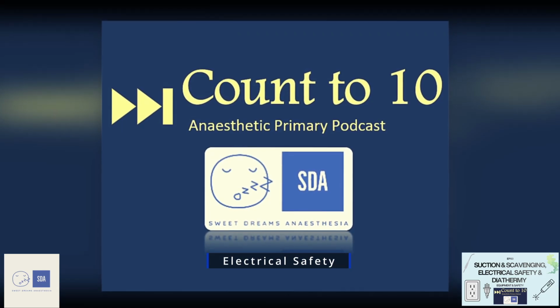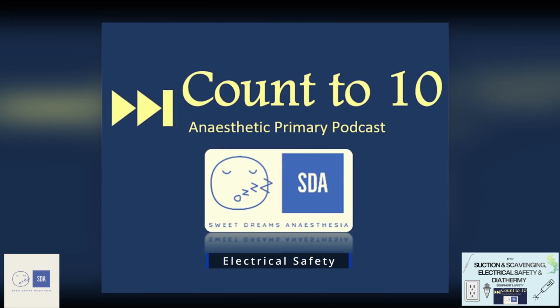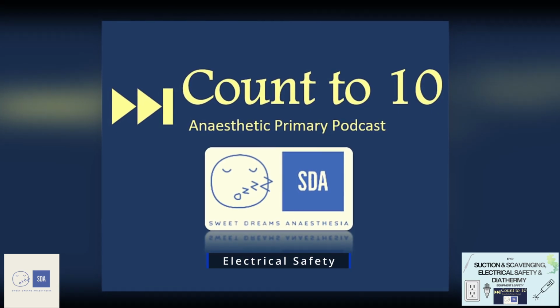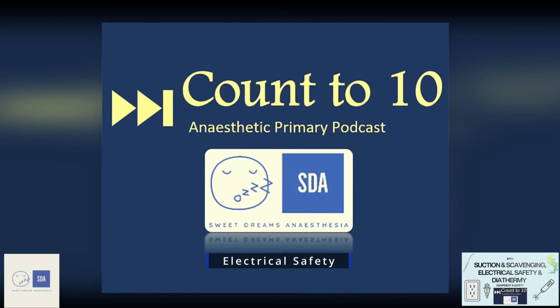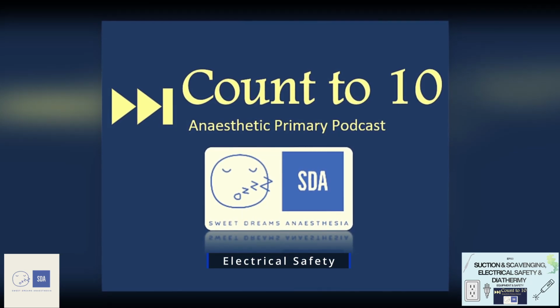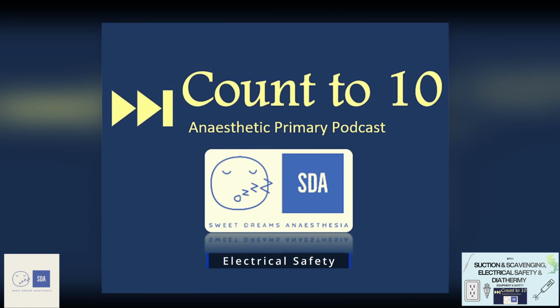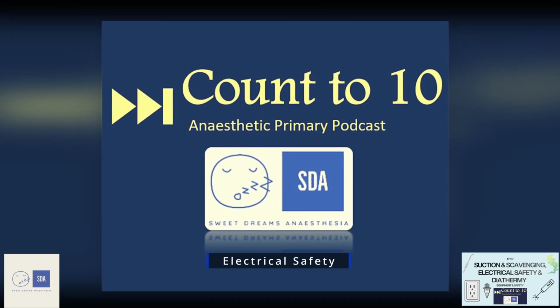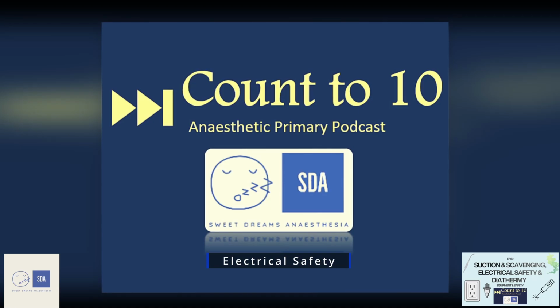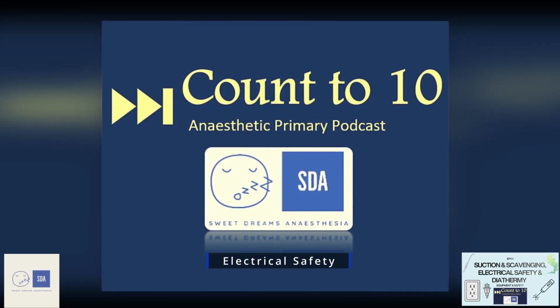Now, on a side note, you'll notice that in the theatre, you have different colors of power sockets. You have red or blue, and then you have the white for cleaning purposes only. What differentiates the red from the blue is that the red power point is connected to a secondary power supply. So in case of an emergency, it will continue to work through a backup generator, which means that you might have the tiniest of delays if the main power fails.